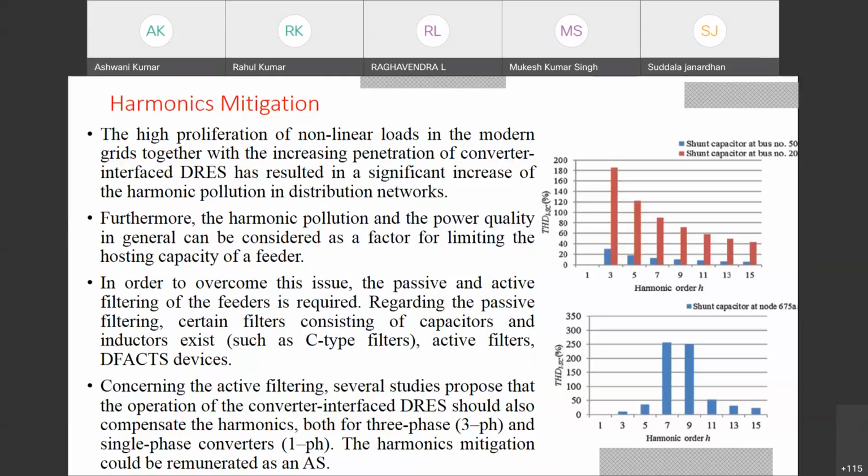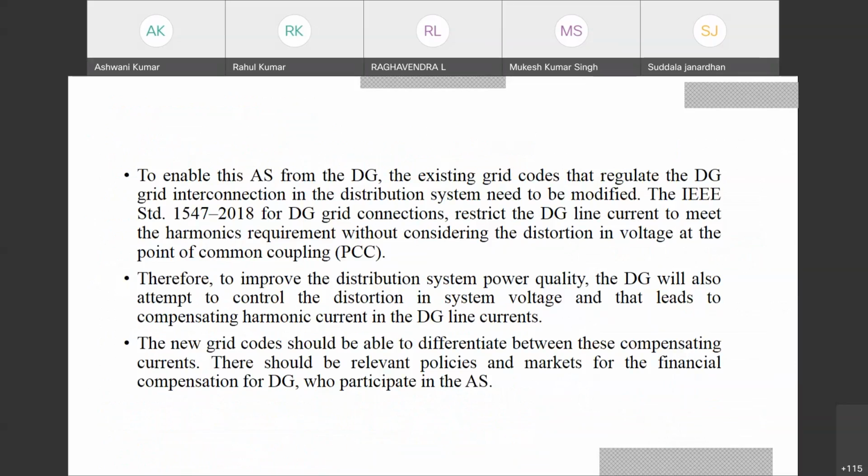So harmonic mitigation is coming out to be one of the ancillary services. These are the standards, like IEEE standards, especially on the distribution side, and these standards need to be modified. You can have a look at the standards and see that within 5%, as an IEEE standard, is the tolerable total harmonic distortion that needs to be obeyed in a distribution system.